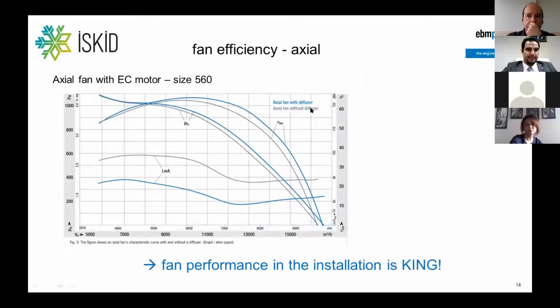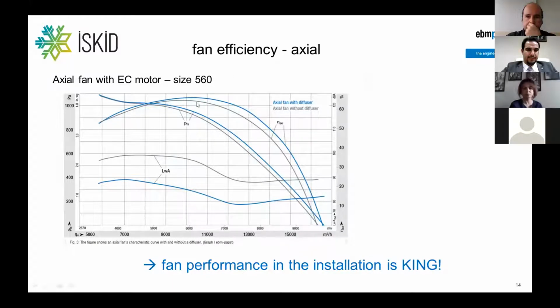Here we tested an axial fan, which is a very efficient one in this case. It has a static efficiency of slightly above 60% with diffuser and without diffuser. The diffuser regains a certain amount of the dynamic energy. But you cannot tell which is the best fan without knowing how the installation is done. I will come to that a little bit later when it's time to talk about system effect.